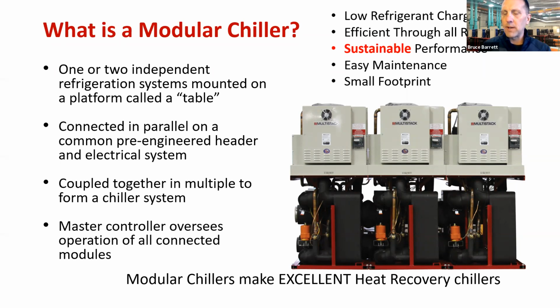We can unload to very low levels. If you need low amounts of reheat, we can deliver that quality of hot water without sacrificing kW per ton. A large shell and tube machine cannot unload very well and deliver that quantity and quality. Also save some pump energy. If you've got a larger array, we can unload to single modules. So excellent use of a modular machine to do heat recovery, both on the performance side, the energy side, and the temperature side for quality of temp.